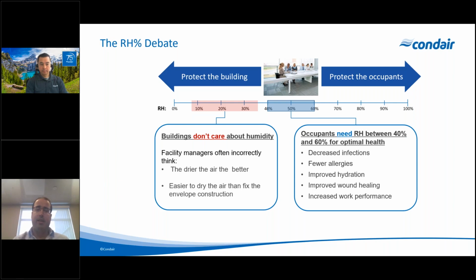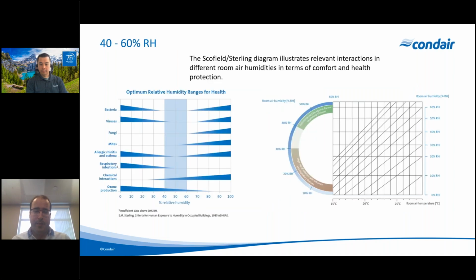The recommendation is always 40 to 60%, that's where most studies show optimal conditions for human health and indoor air quality. For some buildings you might shift a bit to the left, toward 30%, but if your building focuses only on that side, it means the concern is just the building and maintenance, not the people or absenteeism. Even if you save money on maintenance, if you have more sick leave and absenteeism, it offsets all those savings. Sometimes the left arm doesn't talk to the right arm, but absenteeism typically costs much more than building maintenance.